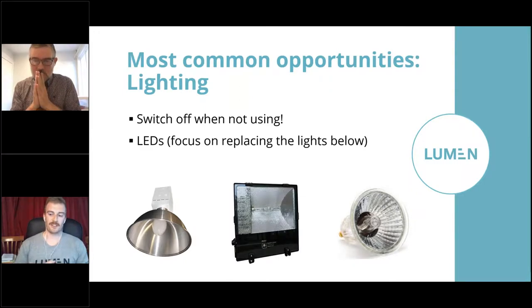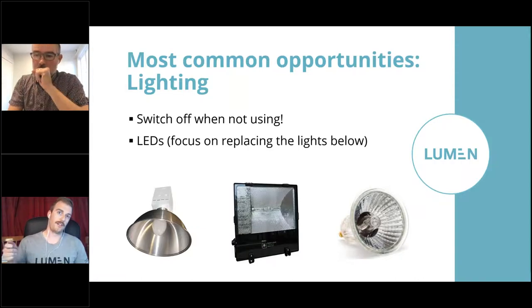We've had some instances with one of our airport clients, for example, where they've got a whole terminal of lighting that's set up on the BMS to run on schedules. And what we found is that they'd left the controls in manual mode on the switchboard. So the BMS was telling the lighting to switch on and off, but it wasn't working, so the lights were staying on 24/7. And that was tens of thousands of dollars wasted. It was a simple fix, just flicking those switches from manual to auto so the BMS could control them.